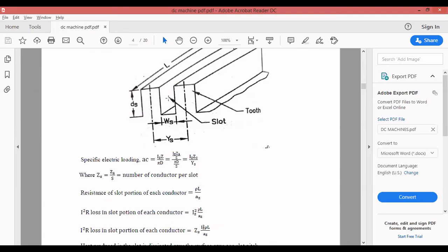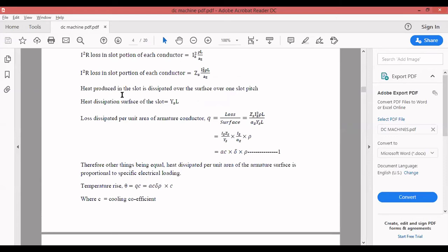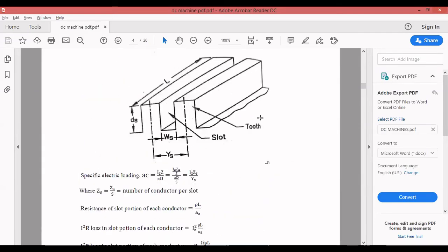So you can sum up that for a particular temperature, a particular value of A_C should be selected. Based on the temperature rise, a particular value of A_C should be selected. The second factor is speed of the machine. For a high speed machine, a higher value of A_C can be selected because ventilation is better, which will dissipate heat at a faster rate, giving higher permissible temperature rise.